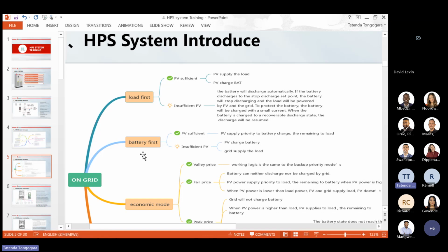And then we have battery first mode. So your battery will always be charged. So it will be charged with PV. If PV is not sufficient, it will be charged with grid. So your battery will always be at 100% if you set the maximum charge SOC to 100%.